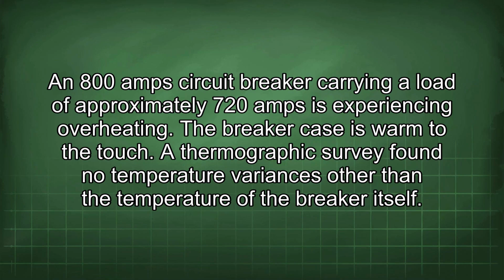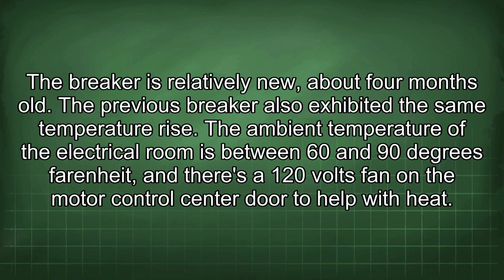An 800 amp circuit breaker carrying a load of approximately 720 amps is experiencing overheating. The breaker case is warm to the touch. A thermographic survey found no temperature variances other than the temperature of the breaker itself. The breaker is relatively new, about 4 months old. The previous breaker also exhibited the same temperature rise.